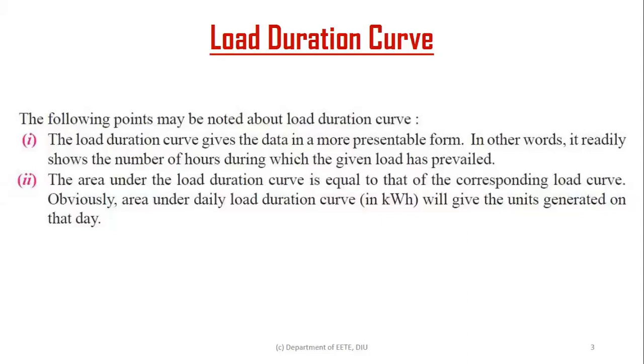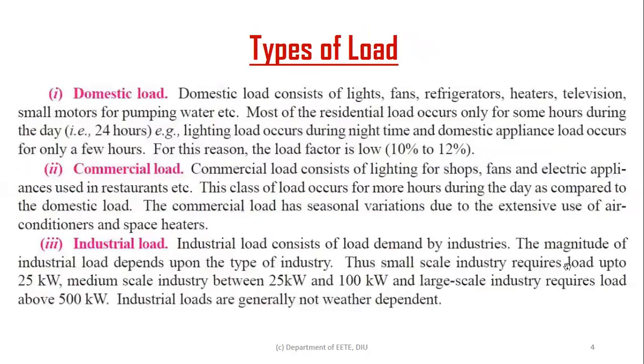The area under the load curve and the load duration curve will give the units generated per day. So if we calculate the whole area, it will give us the amount of units we generated throughout the day. Okay, that was the load duration curve.